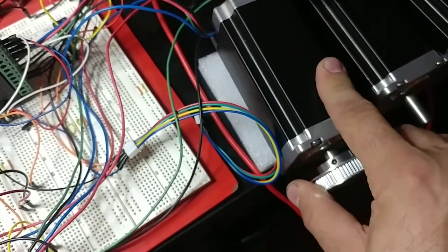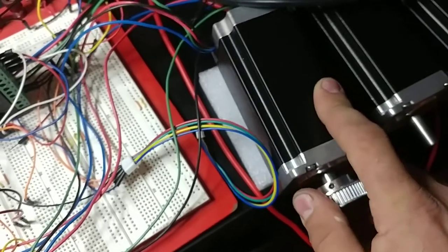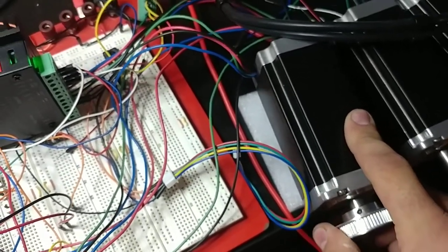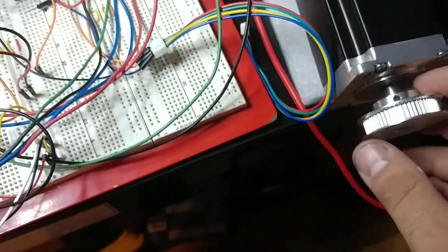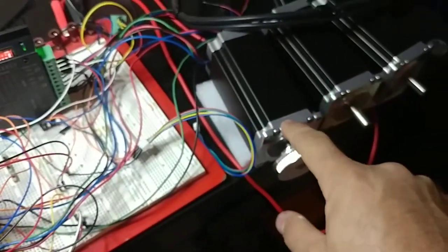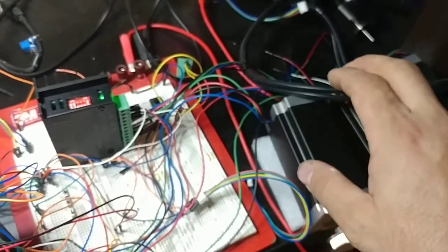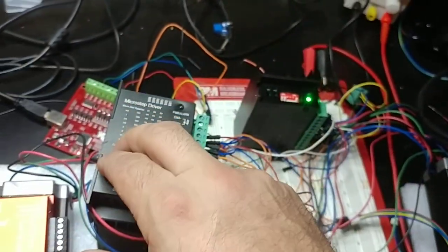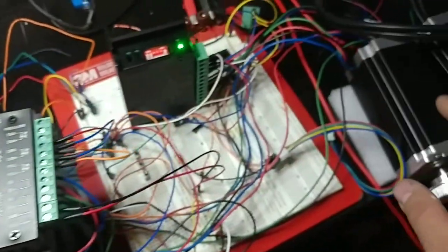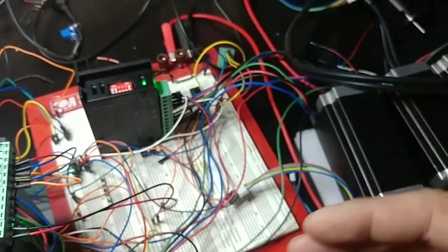So I'm having a hard time turning that. Well, I just got it to turn a little bit. Well, no, actually it just slipped on the shaft. But regardless, if I had a big lever out here, I could just overpower that motor and turn it, you know, 2 or 3 degrees or whatever. Nothing would feed back to the system. My control would have no idea that this motor was turned, and it would continue to operate.